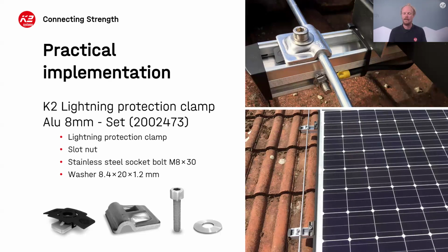So if you are going to have a connection between a copper wire or a copper component and an aluminium product, there is a strong recommendation or maybe even a requirement to use some form of lug, which is specially designed to create a barrier. Whether it's tin-plated or stainless steel doesn't really matter, but the requirement is that the two metal types don't come into direct contact.